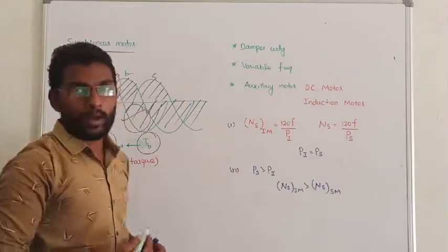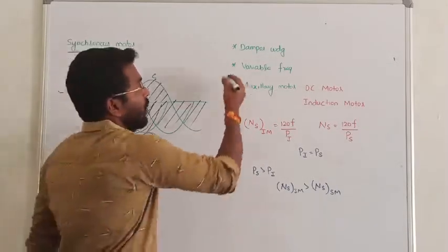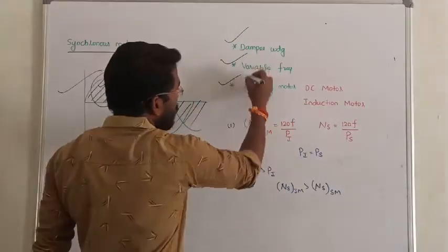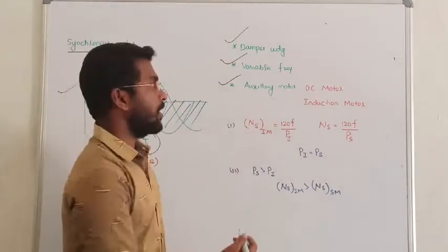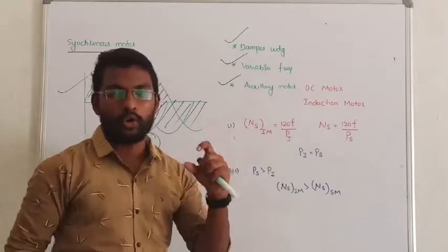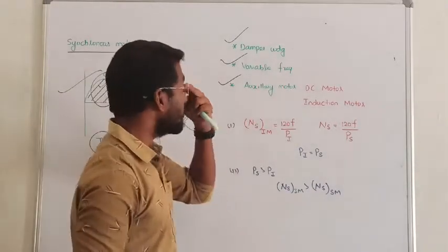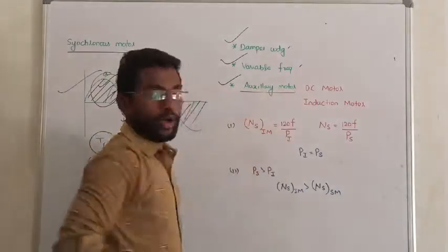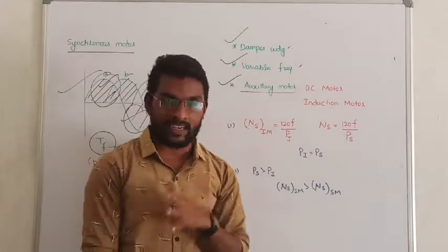To overcome this, or to provide the starting torque in the case of self-starting for a synchronous motor, we are using three methods: damper winding, variable frequency method, and auxiliary motor method. The damper winding acts as an induction motor on empty start. The variable frequency method is also used on empty start. There are three methods: damper winding, variable frequency method, and auxiliary motor.